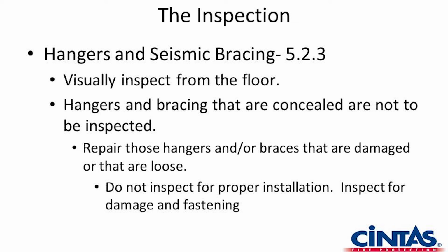Again, it's NFPA 25 telling us that we are not there to call out and say, hey, you need another 25 sprinkler hangers within the building. Just as an example, if pressure within a building is less than 100 pounds, then I can go up to 2 feet on a piece of pipe that runs horizontal over to a sprinkler head. But if the water pressure to the building is over 100 pounds, that lessens that 2 foot down to 1 foot. Now I have to put more hangers in the building. That is something you can look for without making assumptions that he's going to change the design or make you do something that is outside of what the standard says that we're supposed to be looking for.